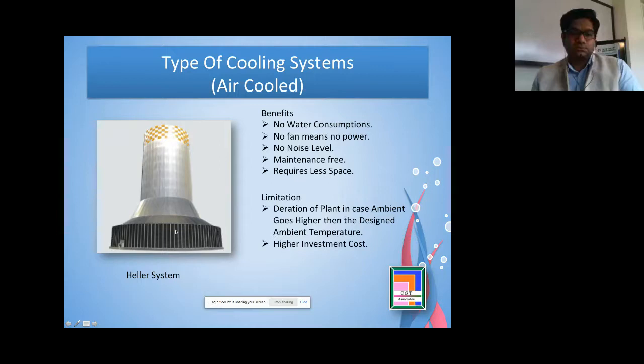And being in a circle, like pi d, it requires a limited area. We also don't have to deal with the heights, where the fans are installed on the top and the repair and maintenance have to be carried out. And some companies, to reduce this height, install the power fans on the side, all around the periphery of this circle, to get that kind of heat transfer. But the limitation is the same: the deration of the plant in case ambient goes higher than the design ambient temperature. And secondly, investment cost is quite high on these ACCs.